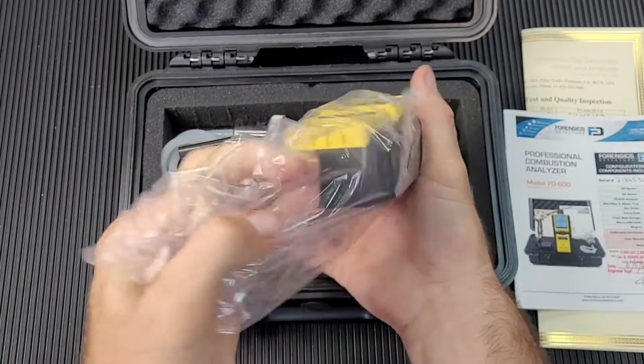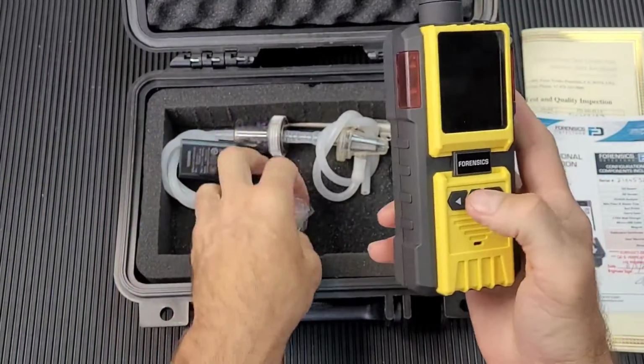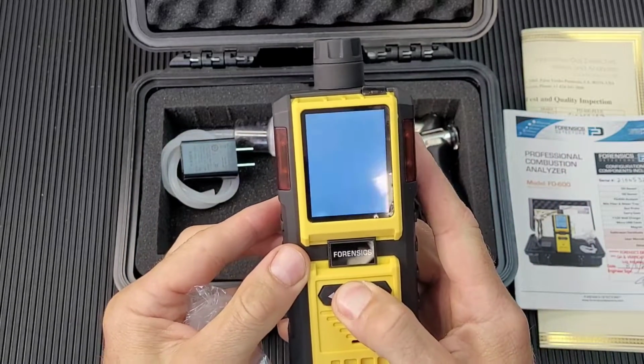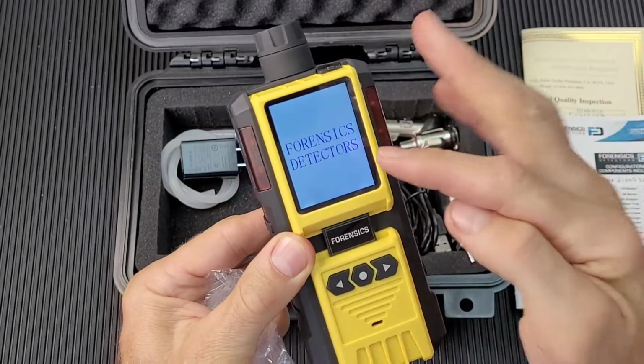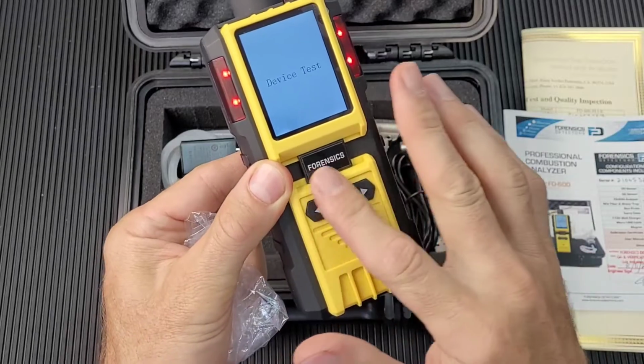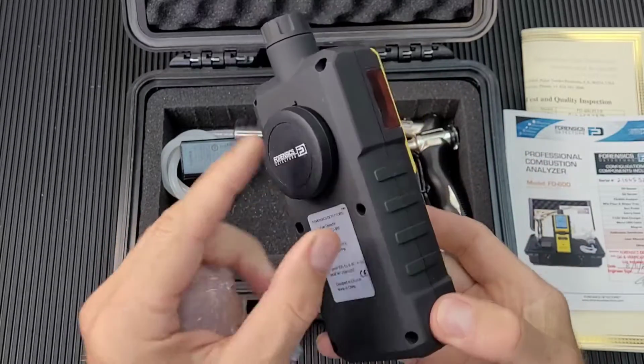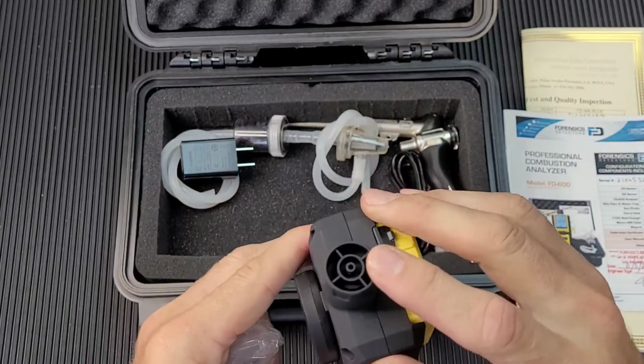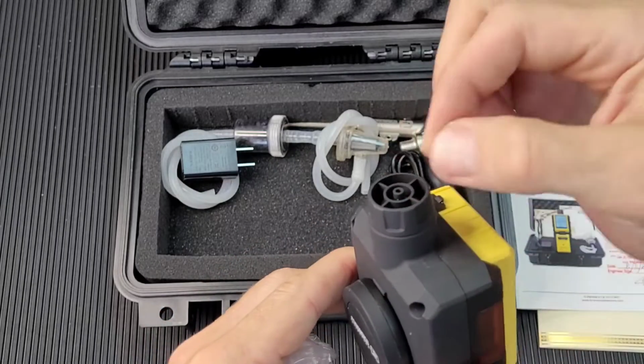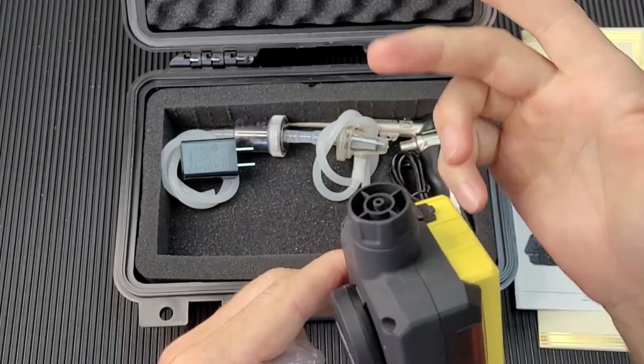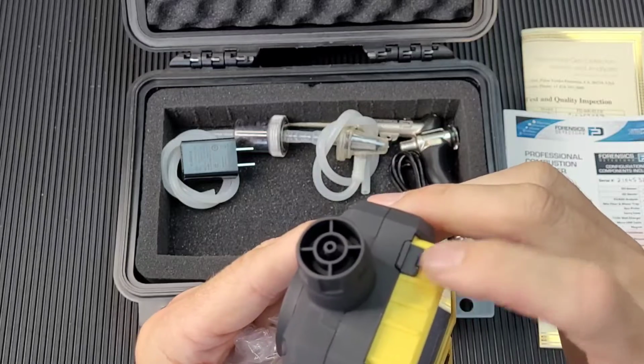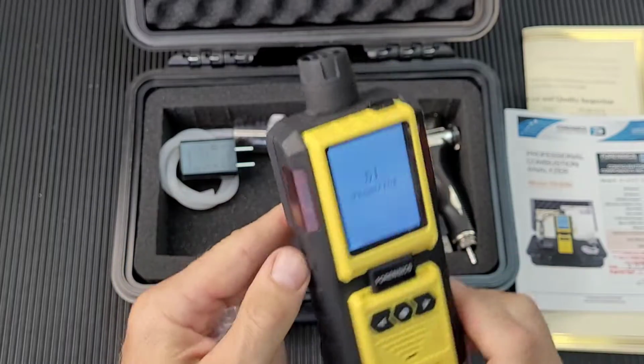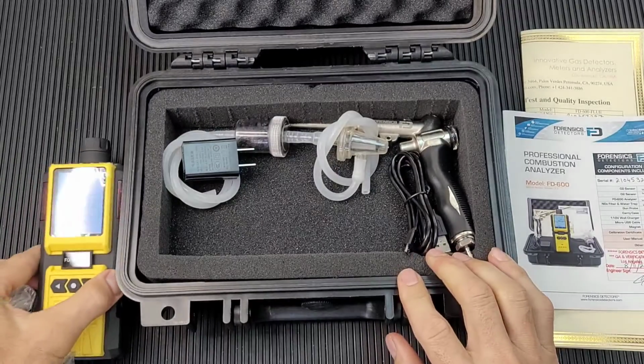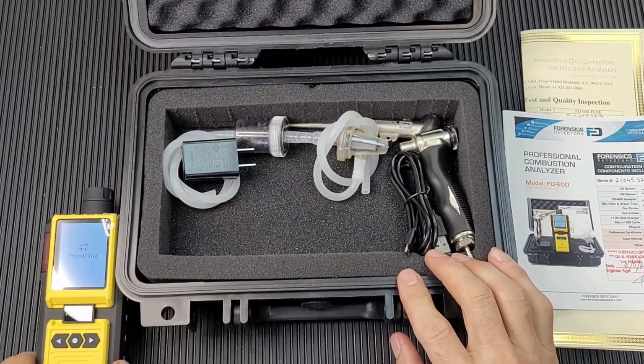Now let's take the mama of all mamas when it comes to analyzers. This is our Model 600 Combustion Analyzer with built-in pump. It has a built-in pump, color screen, as you could see, large buttons so you don't have to mess around. Has a magnet at the back. On top is the barb where you pop in your tube. On/off is very easy. And you have your charging port right there, folks, okay? So let that prepare, let that come on, and you could see that counting down.